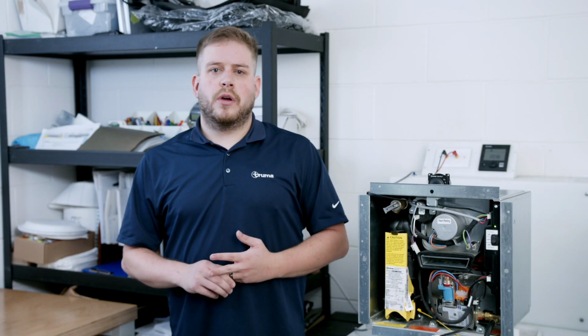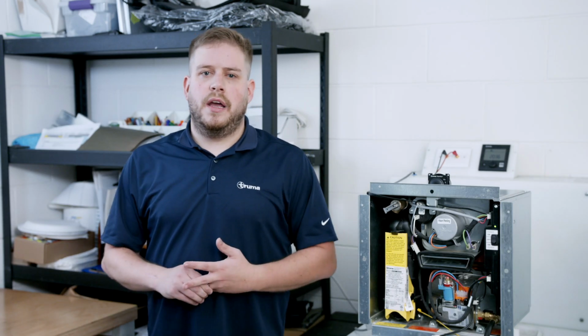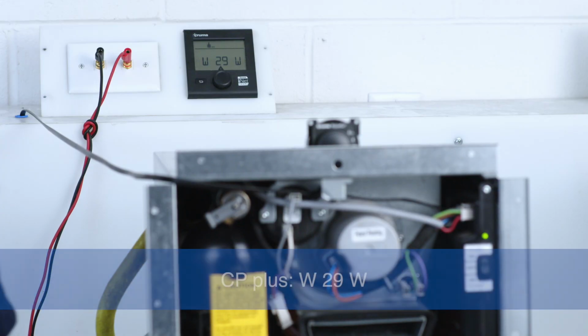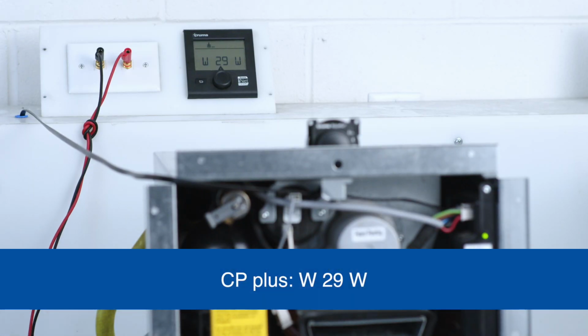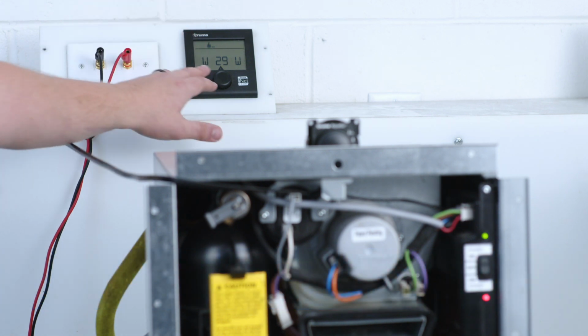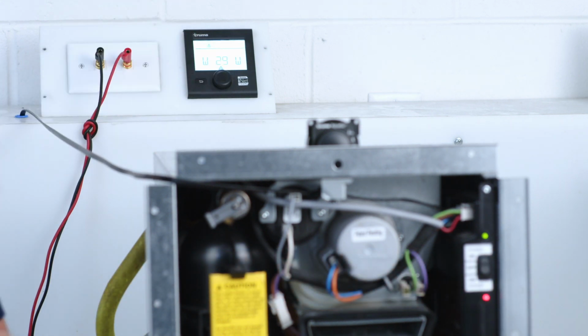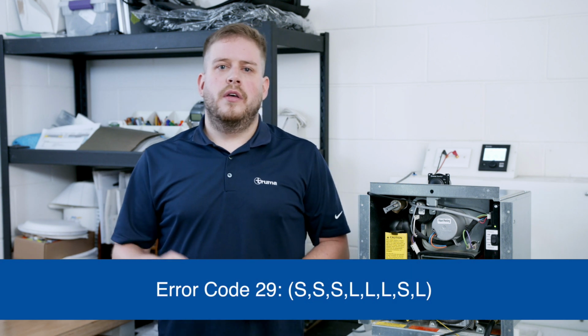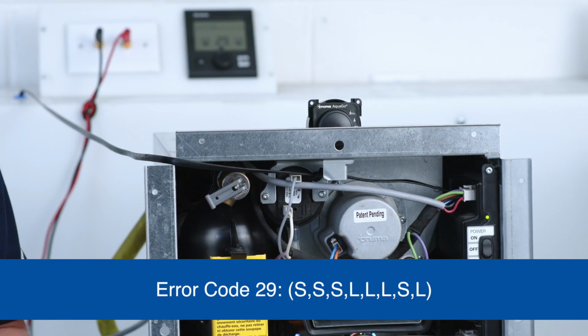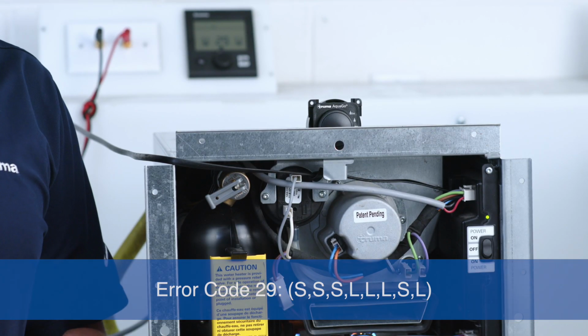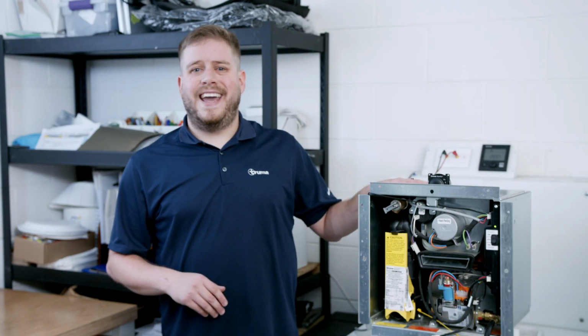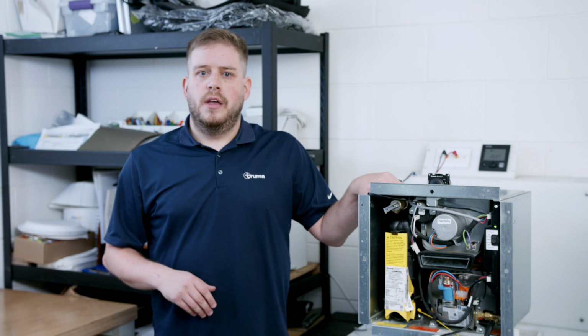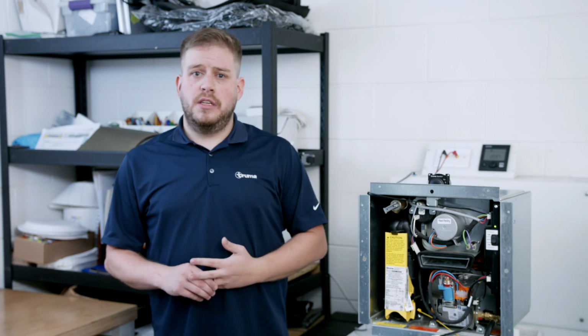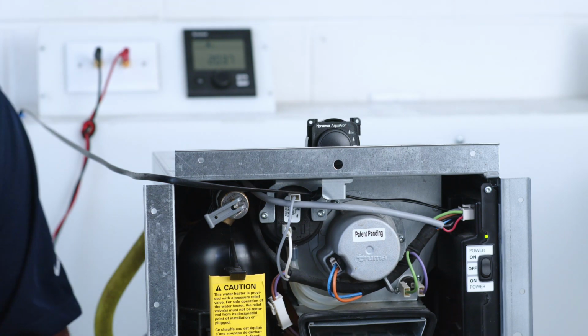The next error code we're going to be talking about is error code 29, too high heat power required. On the CP Plus controller, error code 29 will be displayed as W29W. The dial will display on the control board 3 short, 3 long, 1 short, and 1 long flash for a total of 8. This error code happens because there's too much demand at once on the water heater. It is using its full 60,000 BTUs at the burner and not producing 120 degree water.